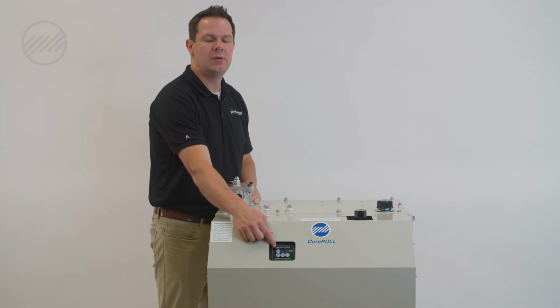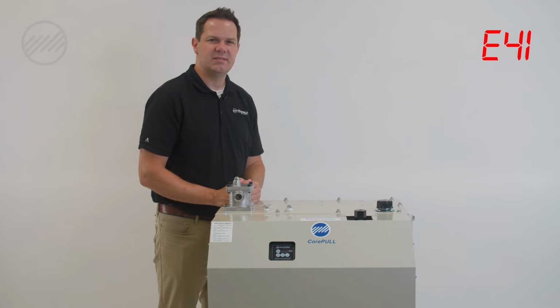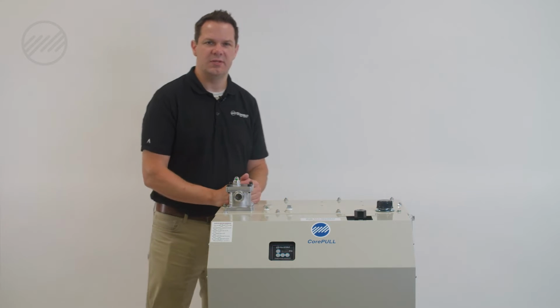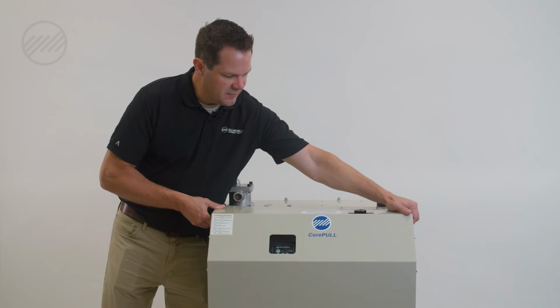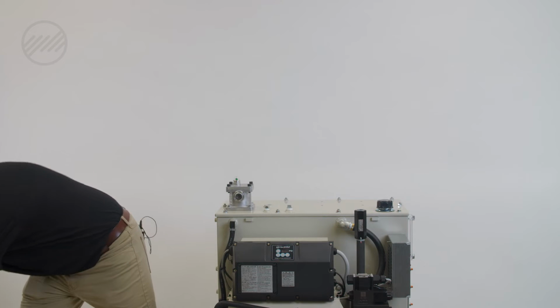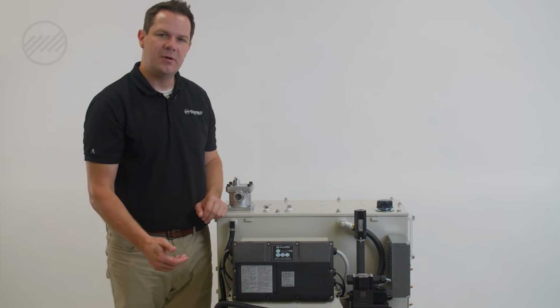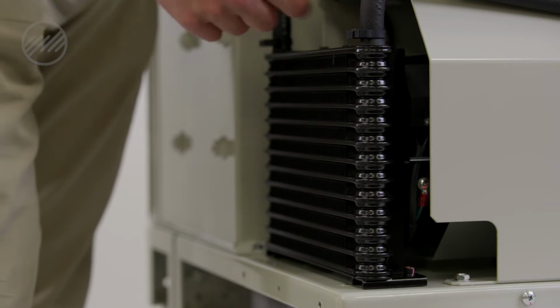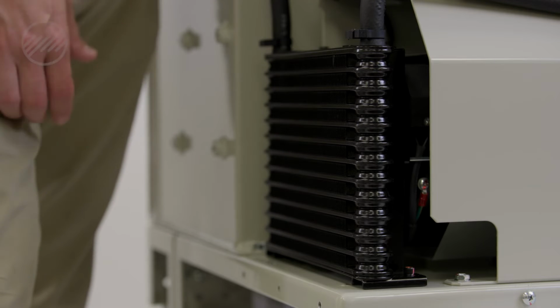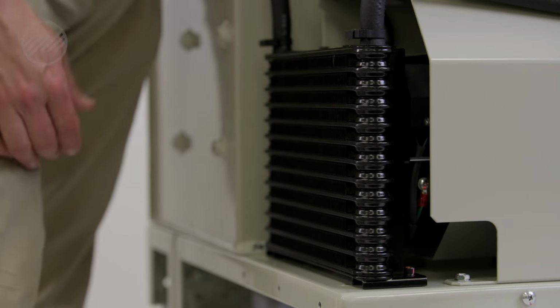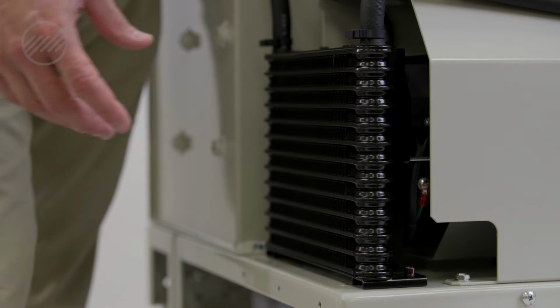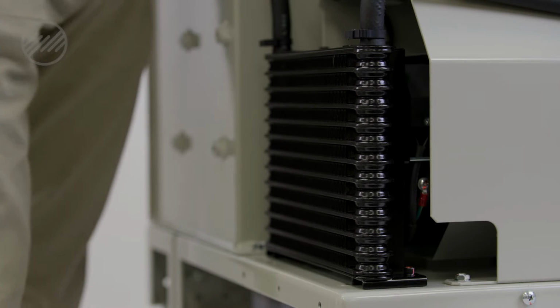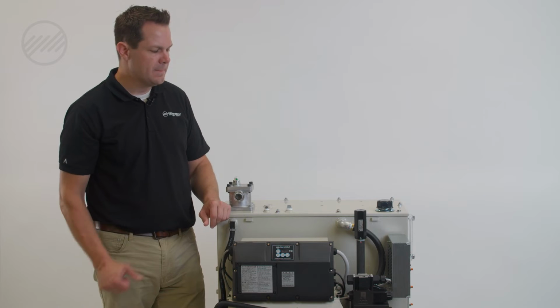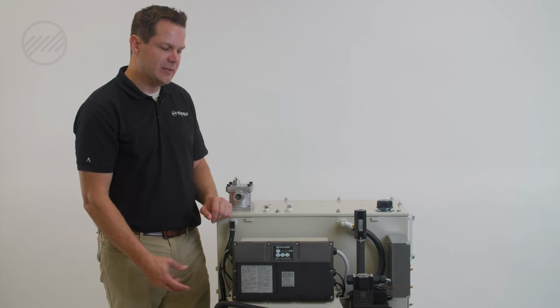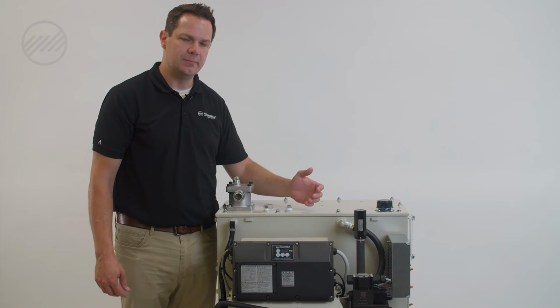If you have an E41 alarm displayed on your controller, this is an indication that your motor temperature has exceeded 85 degrees Celsius. There are several things we can check to fix this alarm. Remove this cover if you have one. First thing we'll want to do is verify our fans are rotating. We have one fan behind our heat exchanger here, and some models have an additional fan over here if you have a cover. If both fans are rotating, we need to make sure that our heat exchanger is not plugged or clogged with debris. If the fans are okay and the heat exchanger is clean, the next thing we want to check is our motor RPM.